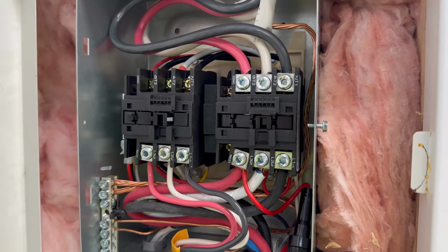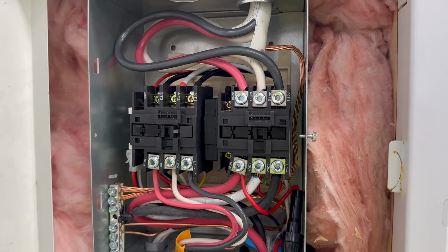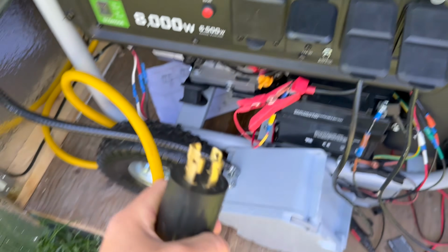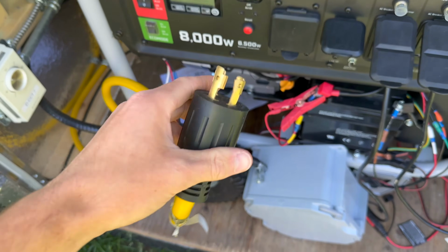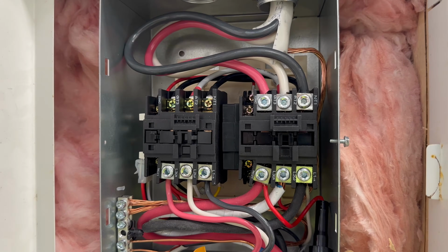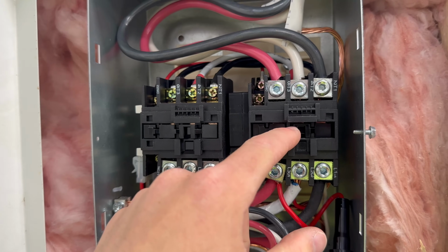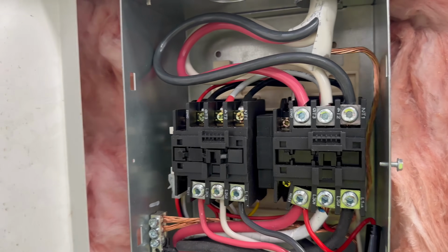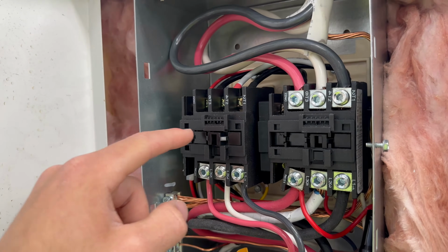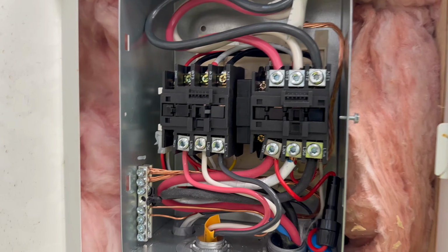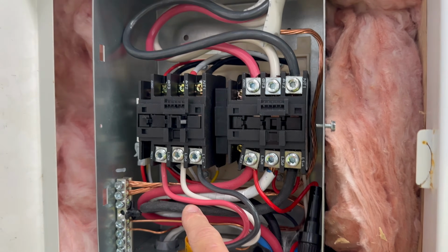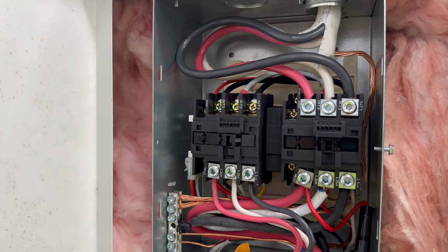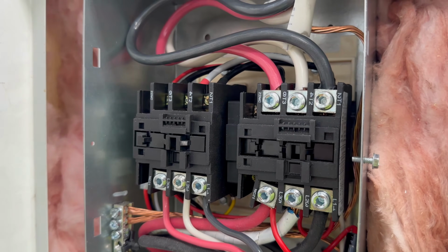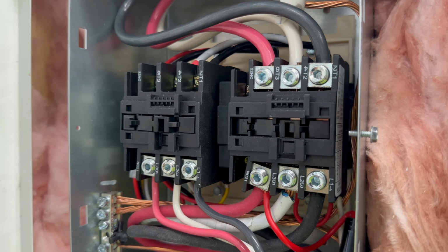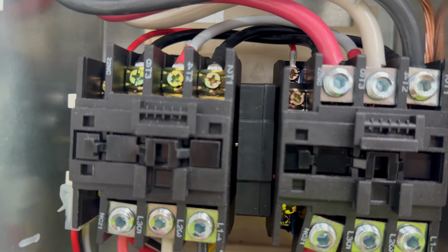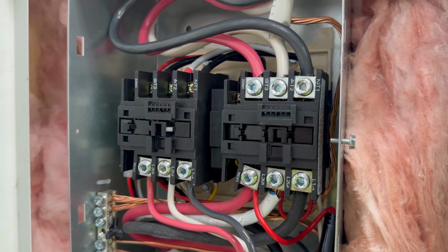It also is important that it is here to make sure that your BC Hydro power never connects to your generator power, as this male receptacle would then become live with 240 volts, and you can see anyone could easily touch that. So how this operates is if the power goes out, this contactor will let go and it will disconnect, and once the generator power is there, this one will close in and then send generator power to the output. Basically, this just selects between generator power or BC Hydro power and will only send one to the output and does not allow them to ever be connected together. So this is not only electronically interlocked where it won't allow them to both be in at the same time, but there's also a metal bar in between, which physically will not let both contactors pull in at the same time.